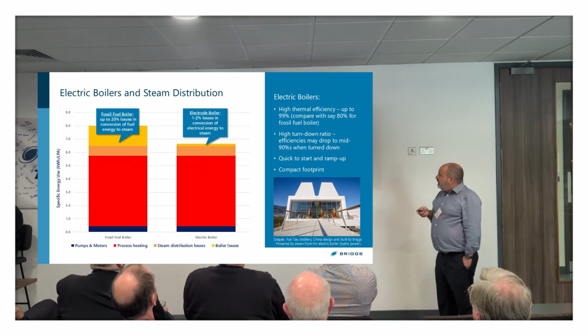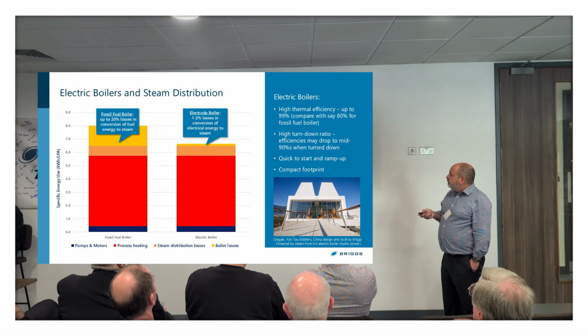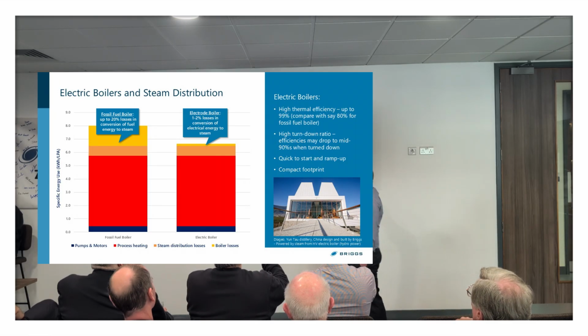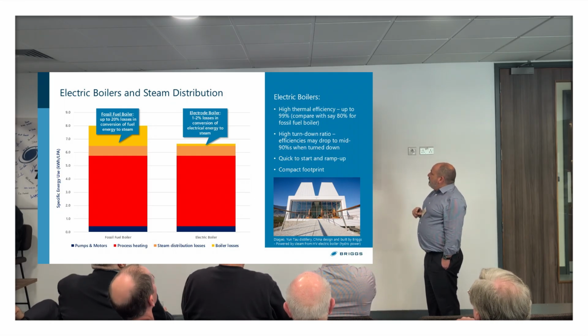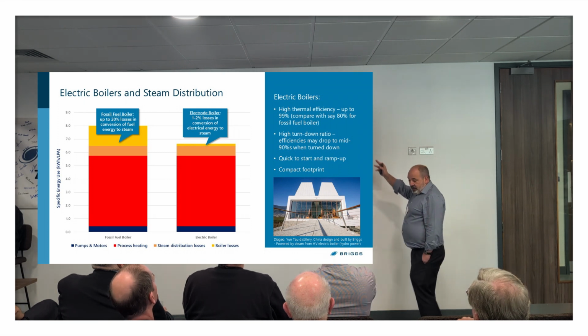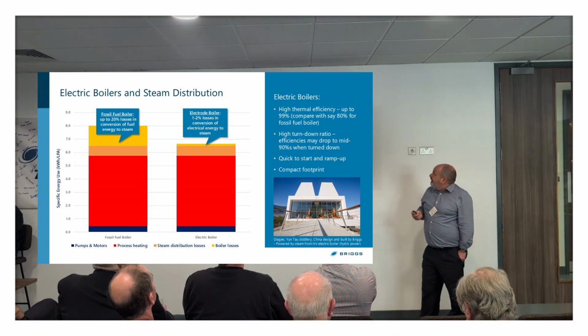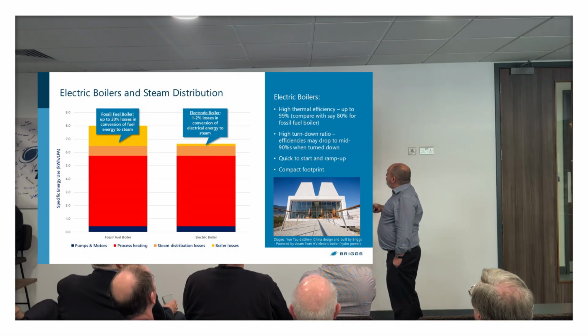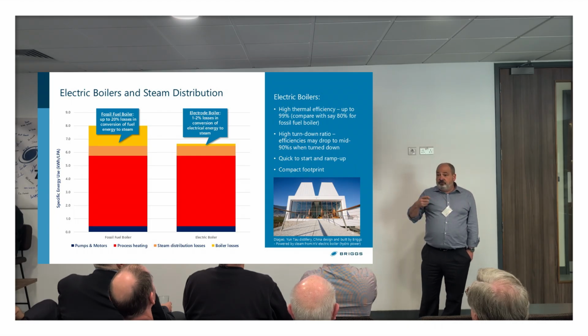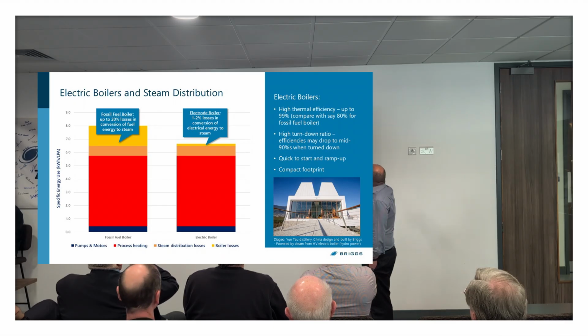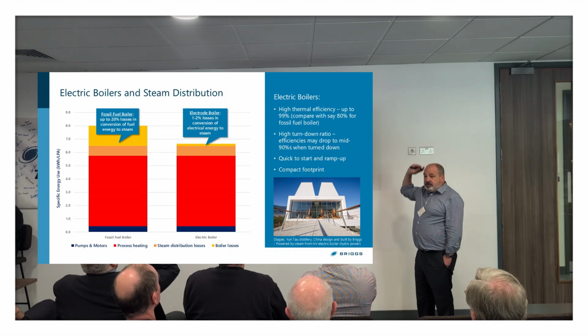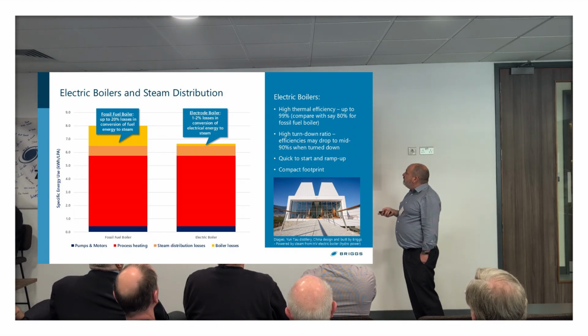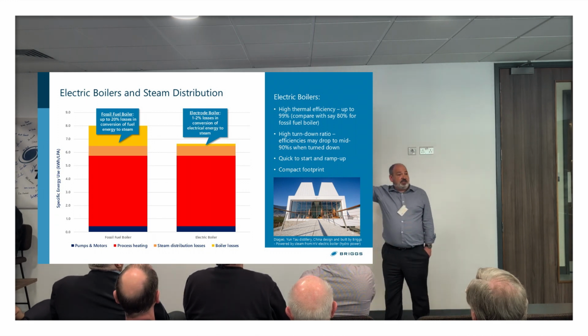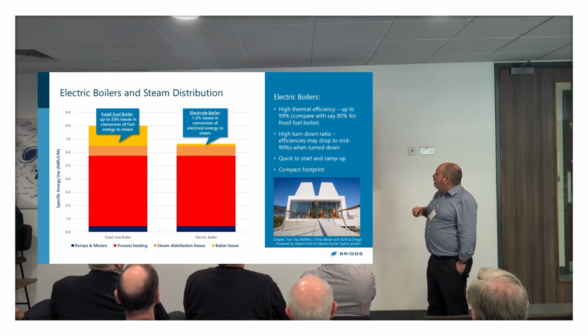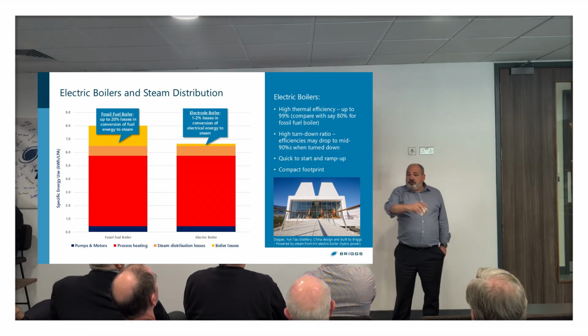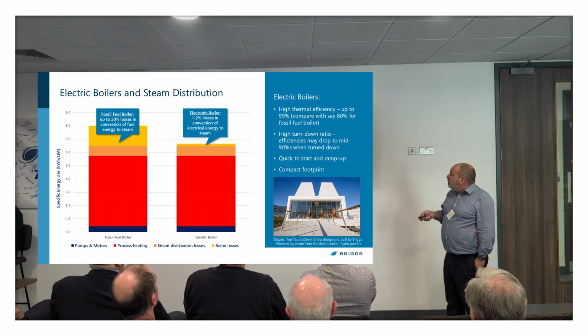Looking at electric boilers in conjunction with steam distribution, it's important to note that the efficiency of an electric boiler is typically much higher than for a fossil fuel boiler. They clearly vary on loading, but a fossil fuel boiler, 80%, 85% efficient, might drop off considerably if it's not fully loaded. But an electric boiler working at its operating capacity is typically 99%. When you turn them down, the efficiency does drop off, to maybe 95%, 94%, but compare that with a fossil fuel boiler operated at 50%, where your efficiency may be down at 65% or so. So considerably more efficient.